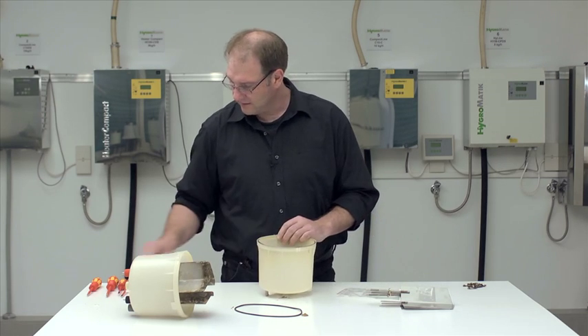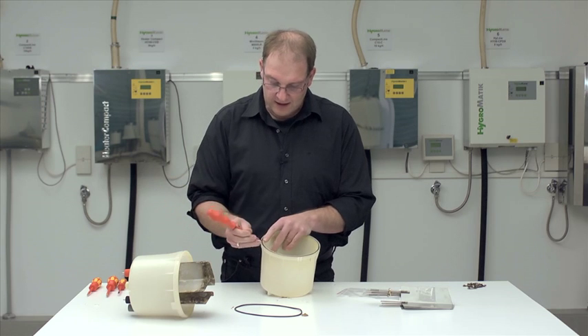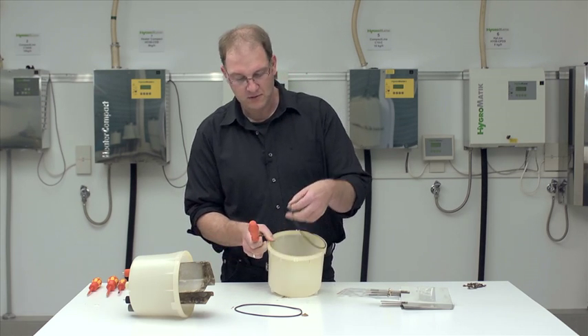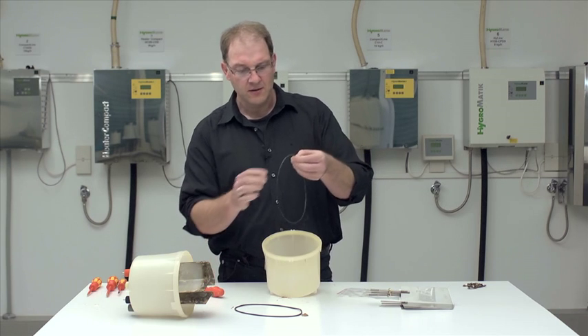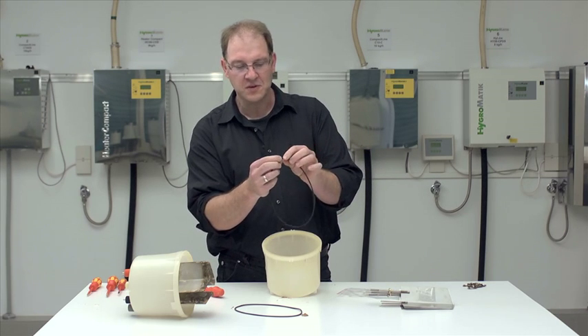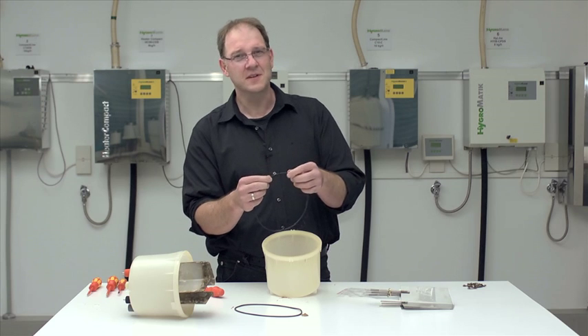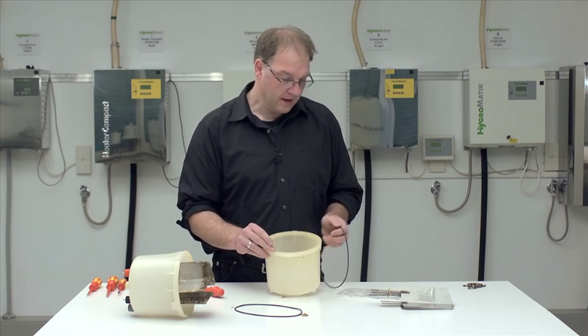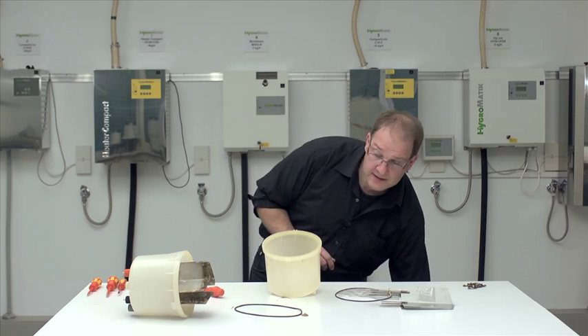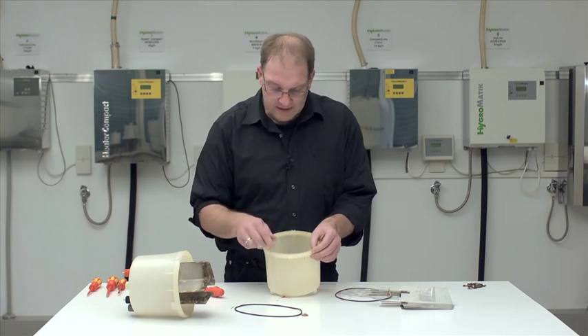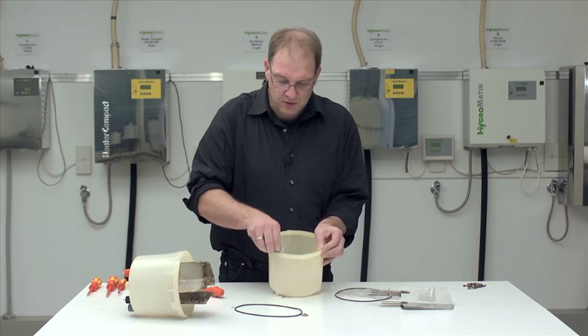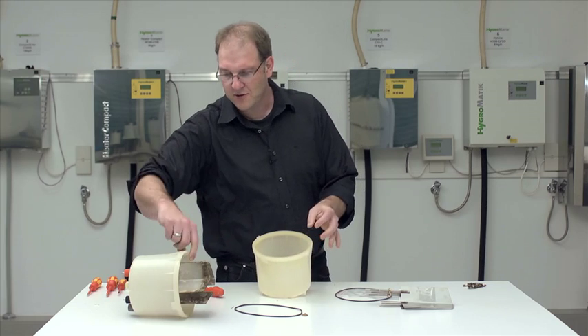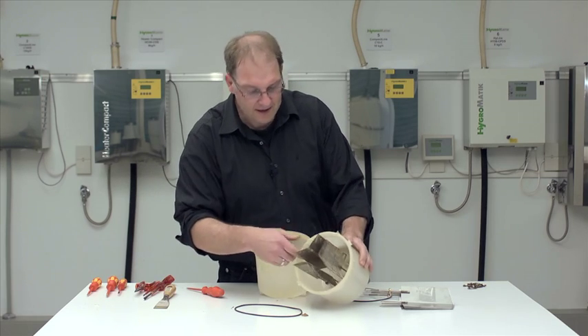Well, I can get the o-ring out of the cylinder flange quite easily. I just take a slotted screwdriver again, pick underneath it, and there it is in my hand. You can feel it. It already is kind of misshapen, and it would be difficult to return this o-ring back to its prior position. And before I just insert the o-ring, I need to make sure that the flange area, the groove where the o-ring is seated, is absolutely deposit free, so small grains of buildup somewhere don't interfere with the seal later.